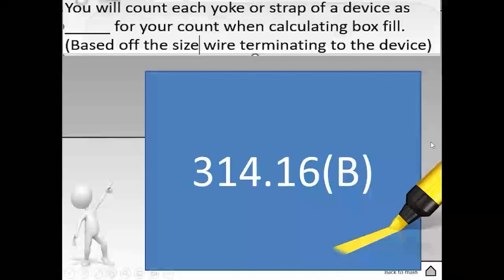To find this, we head to 314.16(B), specifically 314.16(B)(4). I recommend strategic highlighting in your codebook. When you get to B4, highlight the words 'each yoke or strap' in the first line. Then in the second or third line — depending on your code cycle — highlight the words 'double volume allowance.' A few more lines down, highlight the words 'based off the largest conductor connected to the device.' Then go back up to part four and highlight the bold heading. Your highlighting will read: device or equipment fill — each yoke or strap — double volume — based off the largest conductor terminated to the device.